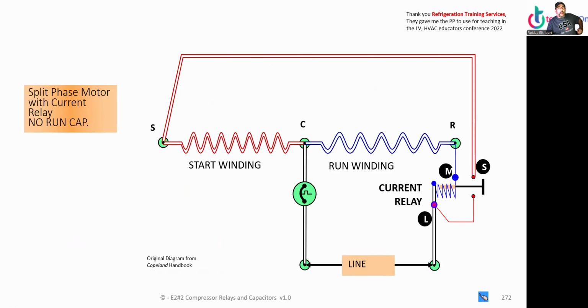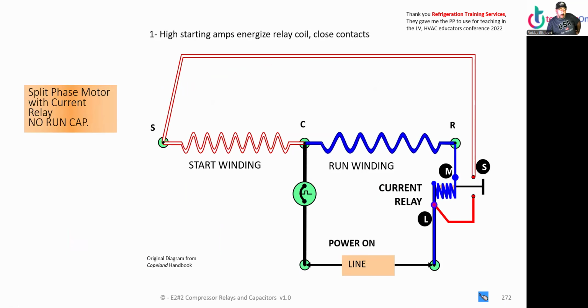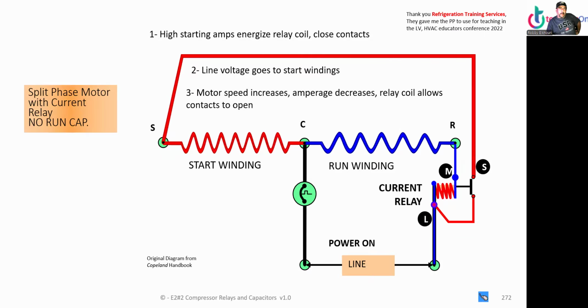All right, now the split phase motor with current relay, no run capacitor. This is the same thing, but a different way of looking at it. Power in, common through the relay coil out to R. We have high starting current. Switch will close. Power will go through the start winding.